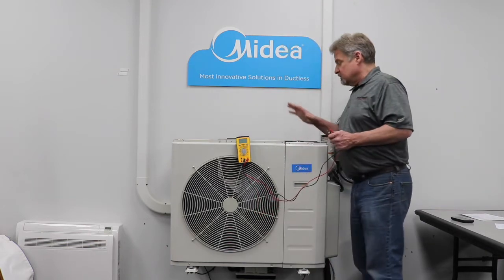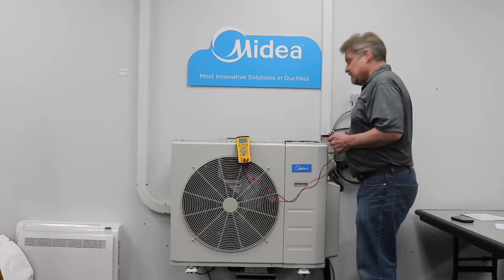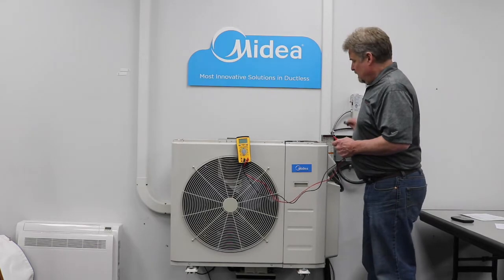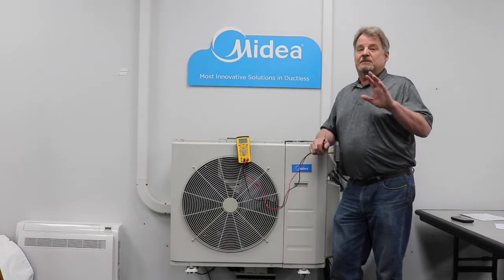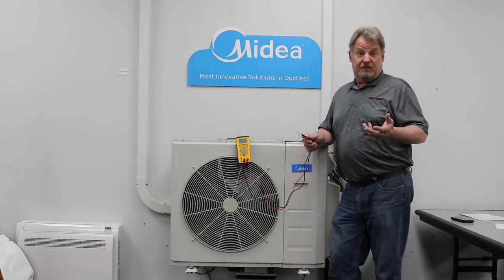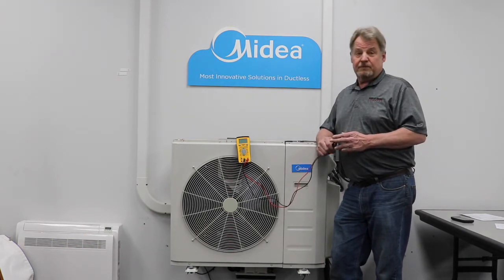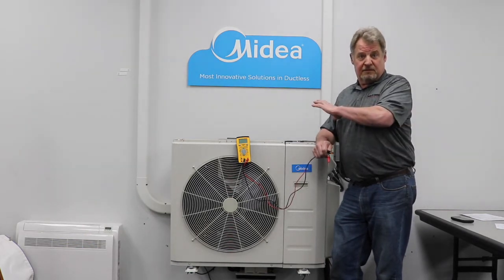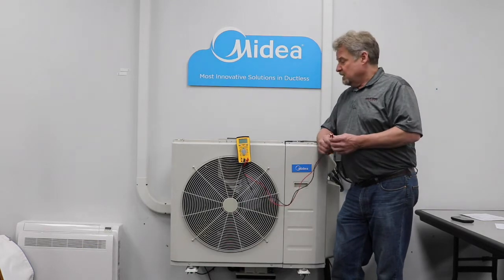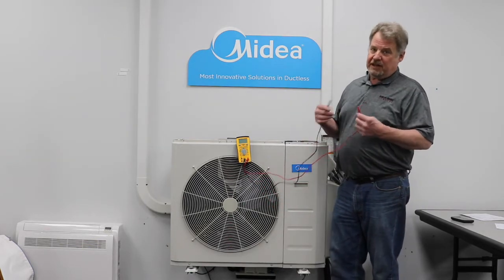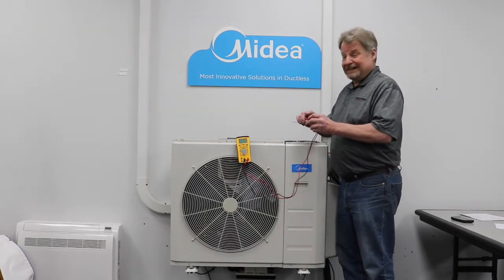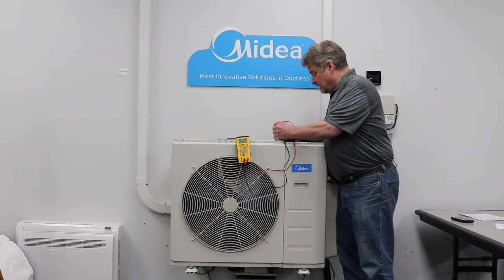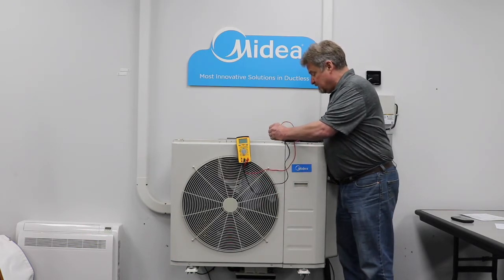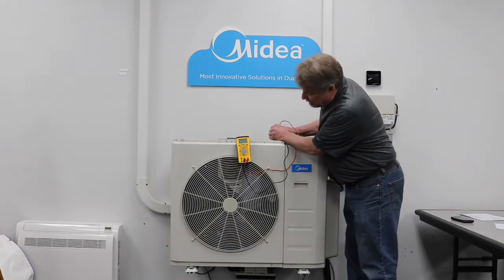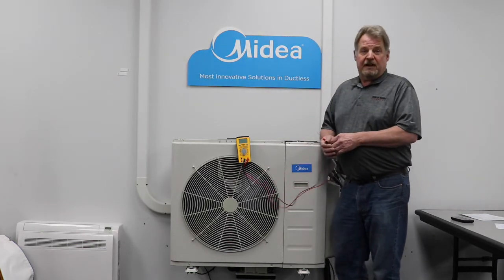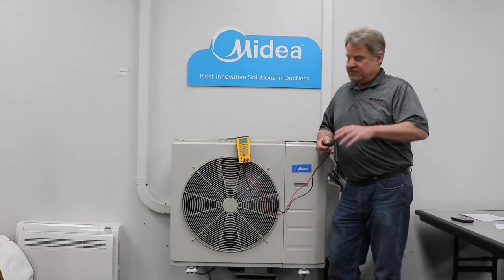First thing I have to do is power down my unit. Those capacitors we just talked about are going to hold a charge, 300 some volts DC, so we don't want to get poked by that. We want to give this thing a few minutes to discharge. If you're impatient like me, before you poke around in there, at least get your meter on there to confirm that yes, indeed, they did discharge. So I go back to my capacitor to make sure my voltage has fallen off and that I've discharged my capacitors.